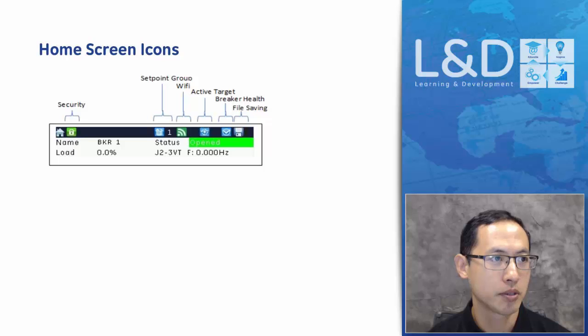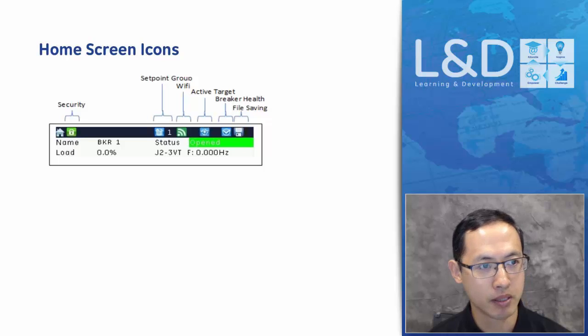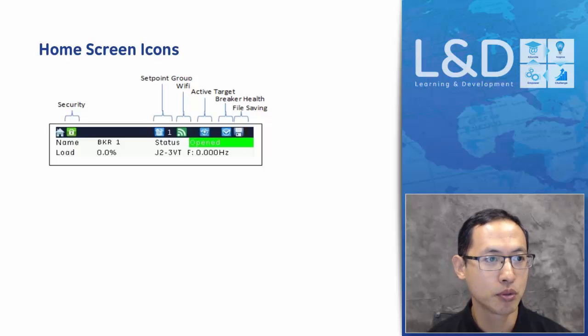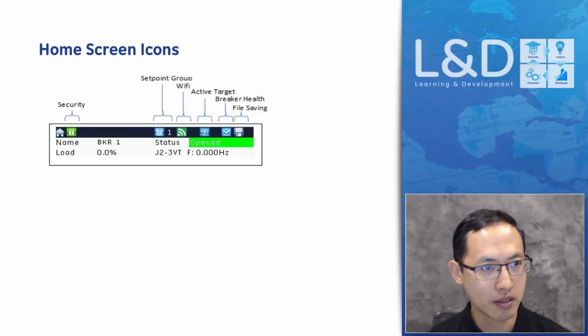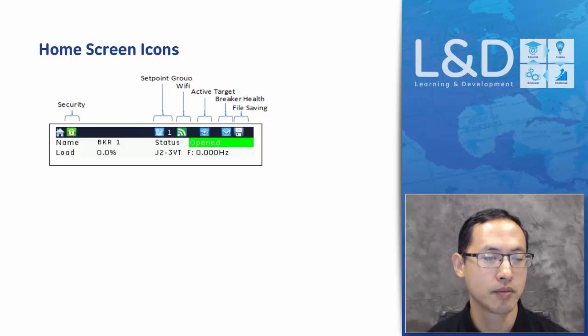On the top of the screen are the home screen icons, which show the status of the relay. You can see the first, security. If it's green, it means it's secure. If it's red, it means unlocked. It also shows the active setpoint group. By default, it's group 1, but this can be changed to group 2 to 6. And it also shows the Wi-Fi status, any active target message, and the breaker status, healthy or unhealthy, and also if a file is saving, it shows that file saving status.